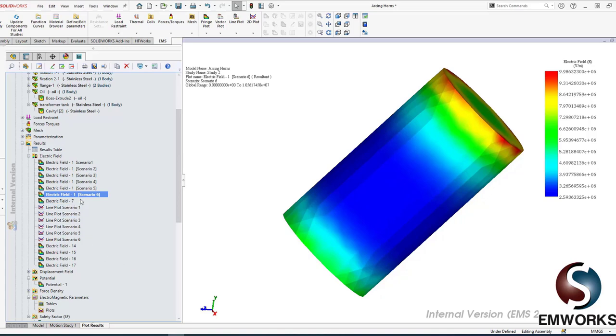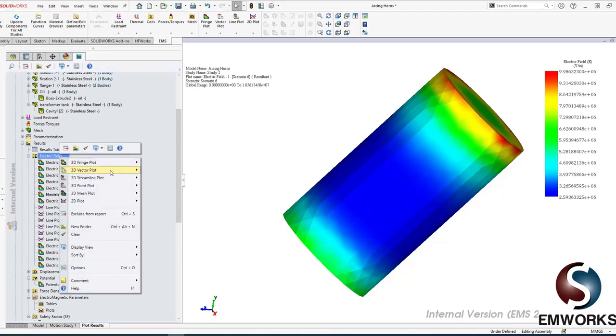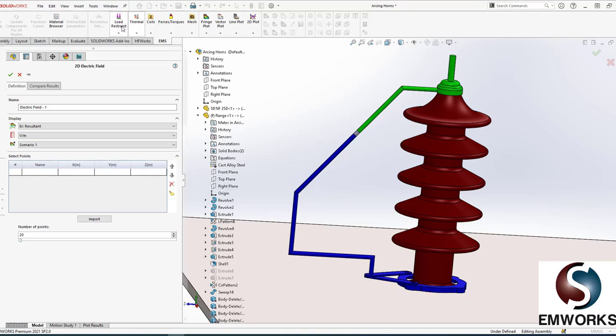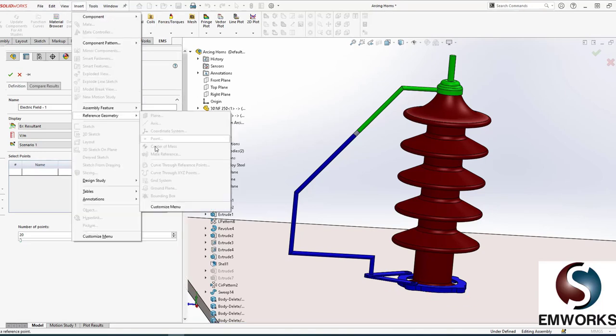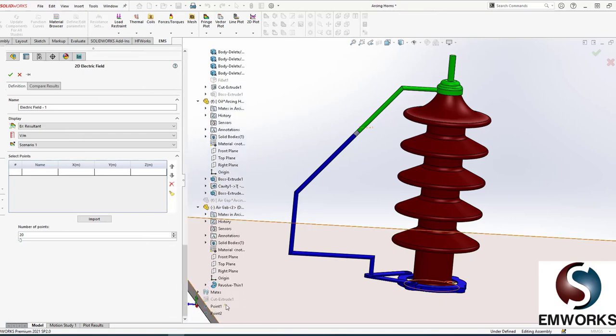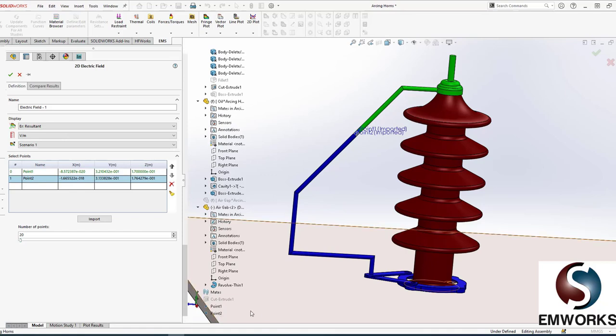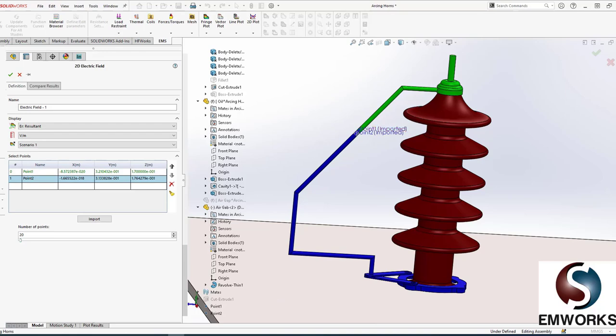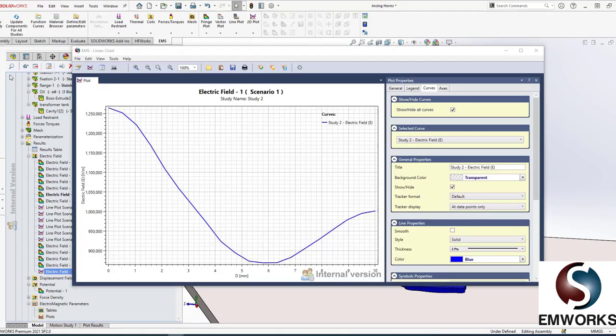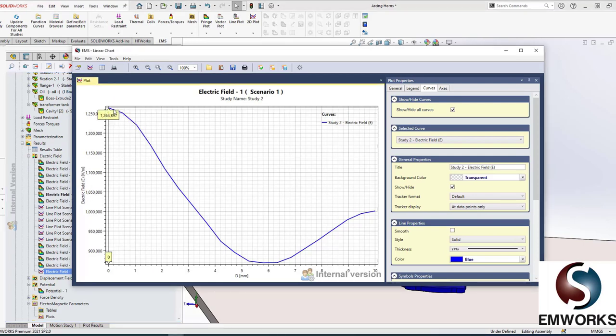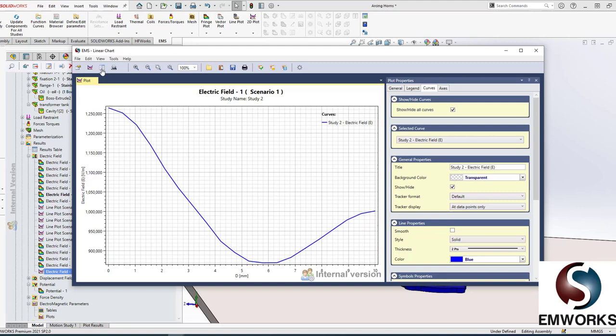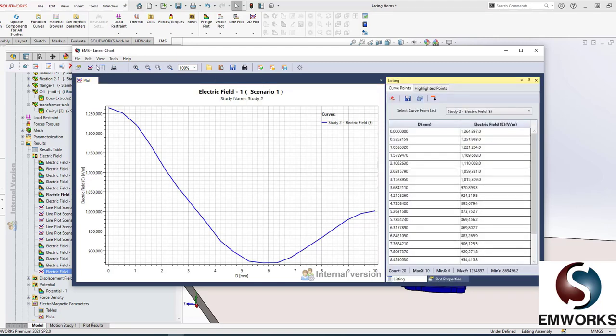Scenario five, again it looks like there is a breakdown all over in the gap, and scenario six as well. Now let's look at scenario one. There is a 2D plot I can do: a linear plot. If I choose, I can insert reference geometry point 1 and point 2. It's straightforward. So point 1 and point 2 are at both ends of the air gap. For scenario one, I can see in the entire air gap there is no breakdown. So that is nice; that's what I want. If I want to see the numerical values, I can see the listing. Of course I can export this to Excel or other data formats.